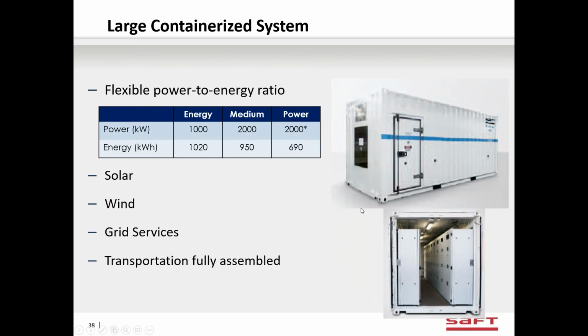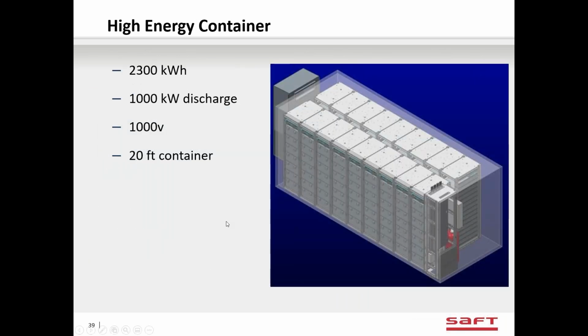And we have a couple of different containers. This one is more designed for power. You can see inside the container, there's a hallway to get in and service the batteries. But that really reduces the energy density because you have so much empty space in the hallway. So in our new design, you access the modules from the outside by doors on the side of the container, and we put much bigger modules in to fill the whole container, so we get a lot more energy in that container. We call it the high energy container.